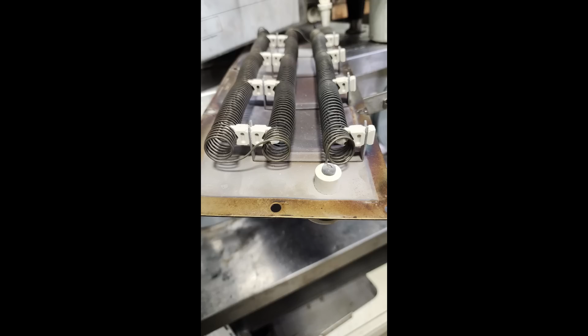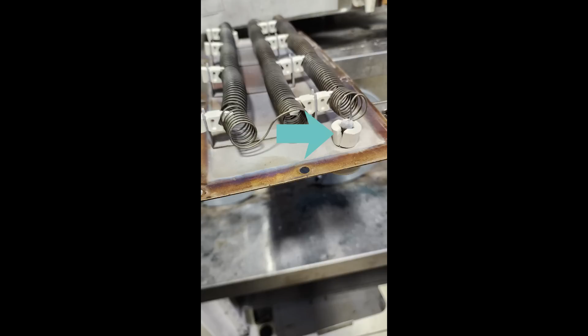But you'll see the one on the other side where it's split - right here, see that split in the ceramic - and the piece of the element is bent out. When that's inside the mesh caged area, it touches against the metal, causing it to short out or arc against the mesh bracket. So that's another of the issues there.